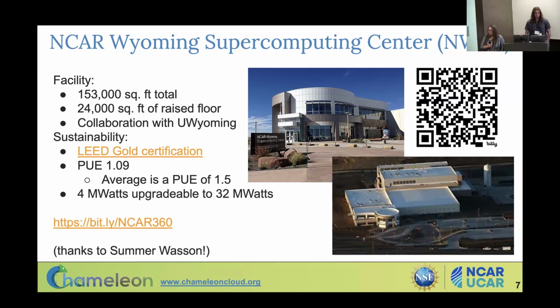What does that mean? It means for every 1 watt that goes to the supercomputer to power it or to the storage system to power it, 9/100ths of a watt will be used for everything else. That's cooling, that's the lights in the building, that's the system for getting into the building, all of that. So it's very efficient. Almost all of our power is going to run the supercomputer, and that's the key for the building. And it's mostly power or cooling that we're concerned with, right? That's usually what's used besides the power for the machine.